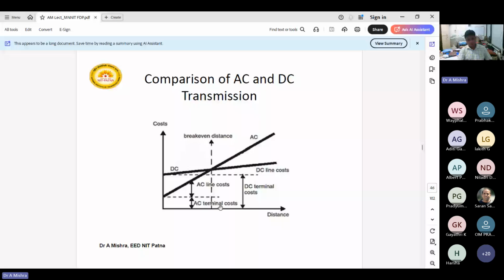But the line cost in DC is very less. Why very less? In case of AC, you require 3 conductors or 6 conductors as per the requirement. But if you are going for the DC side, fewer conductors will be required. 2 conductors are used, for plus and minus. And in certain cases, a single conductor can be used for the transmission and ground used as the return path, which is basically done by the Indian Railway. So in case of DC transmission, it is also possible to use single wire transmission, and the ground path can be used as the return path.